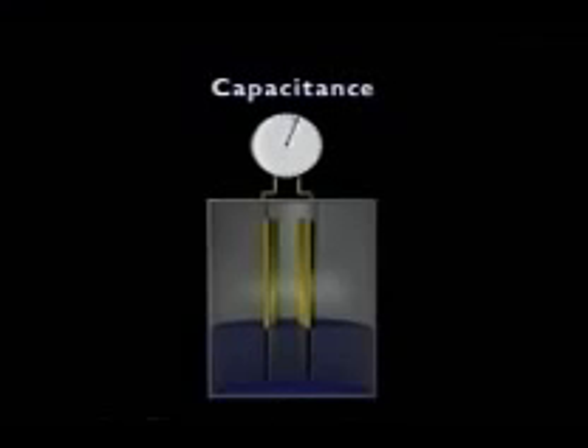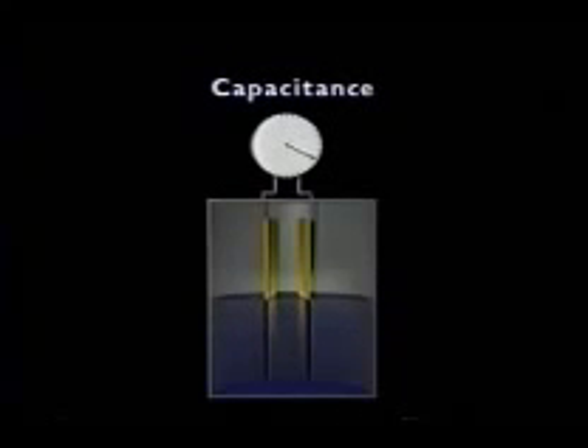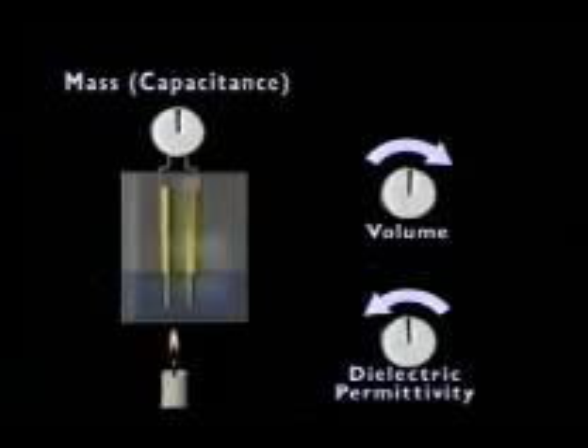We can use this principle by putting plates down into a fuel tank or other liquid tank. If we know the dielectric permittivity of the liquid, as the tank fills, the capacitance of the gauge will change. This turns out to be a nice technique for fuel gauges, particularly in aircraft, because the change in permittivity with temperature is about the same as the change in density of the fuel with temperature. So this can be calibrated to effectively be a mass gauge.